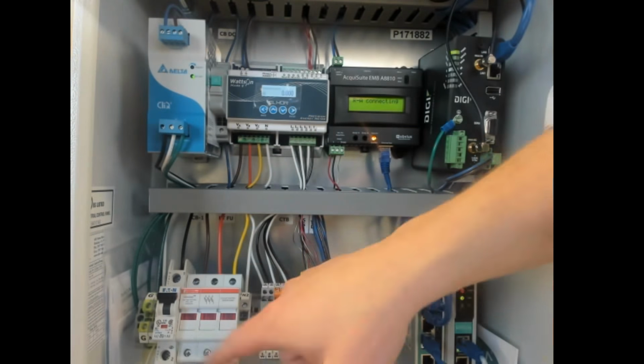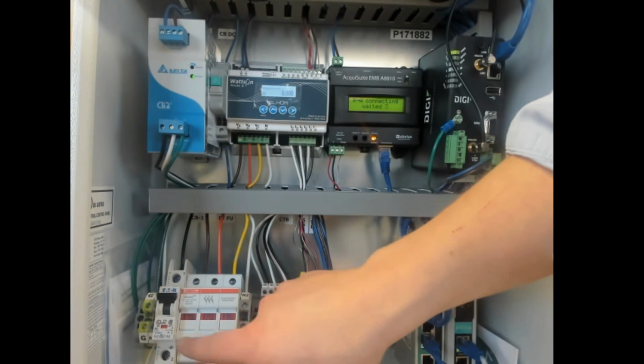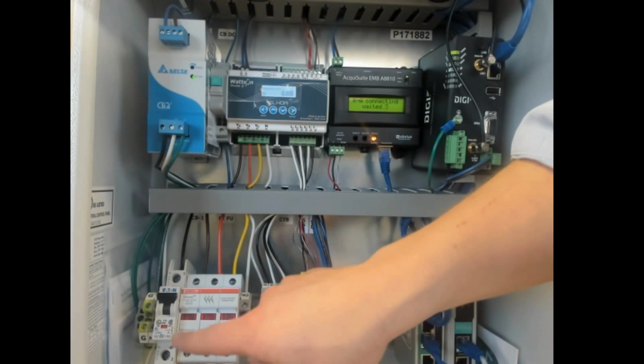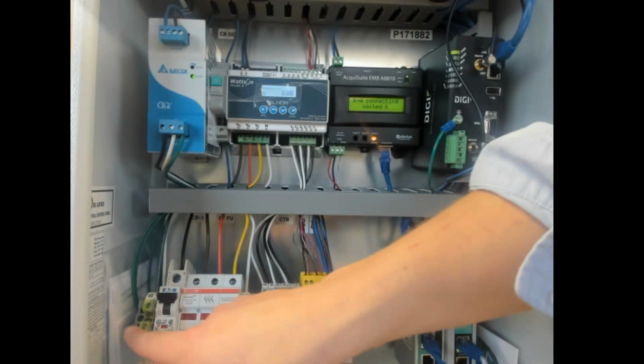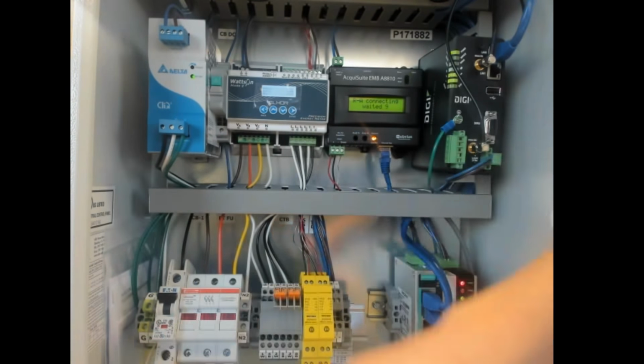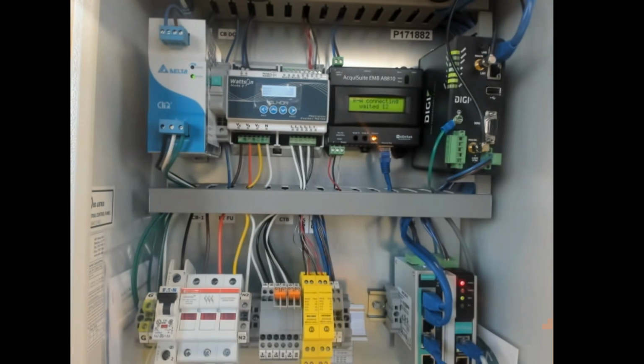But it's very similar in function, and we also have the DC breaker for that. The one difference from the installer's point of view is obviously we'll have a high voltage option available, so you're going to need 2 hot legs, meaning there's going to be a 2-pole breaker just like we do with the 360 now.